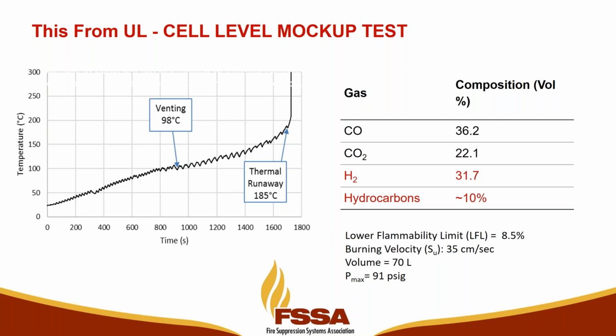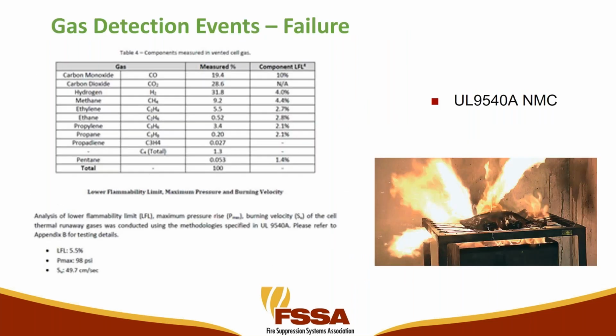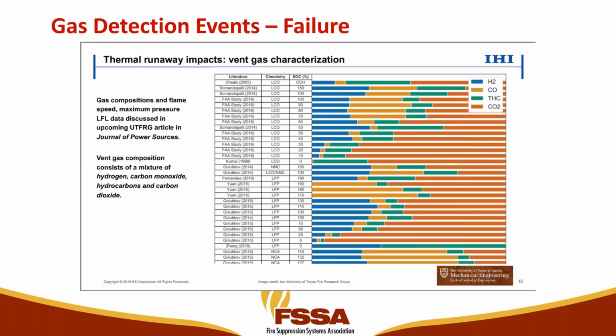They looked at the venting, that's an off-gas event that you move into. But hydrogen was 32%, hydrocarbons 10%. Here's a variety of tests UL has done, again with NMC, nickel, manganese, cobalt, where we got about 32% hydrogen.